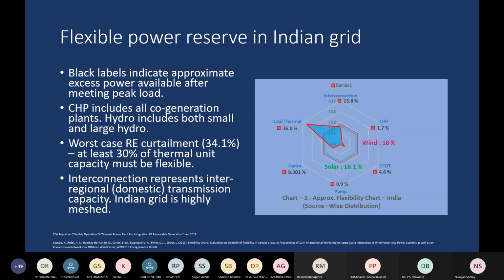So in India, this is the flexibility chart for India, on the right. If you look at the interconnection, it is about 15%, 16%. In India, coal thermal is expected to be the flexible resource. When I talk about flexible resource, I mean that when the wind is going to ramp down, or when the solar is going to ramp up or ramp down, which resource is going to step in and take up that amount of generation. So in India, it is expected that the coal thermal, which is fossil fuel based, is what is expected to be the flexible power reserve.